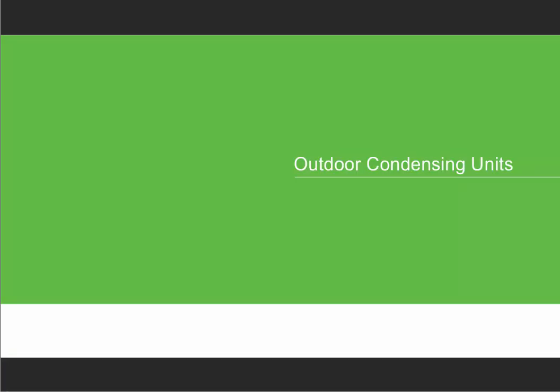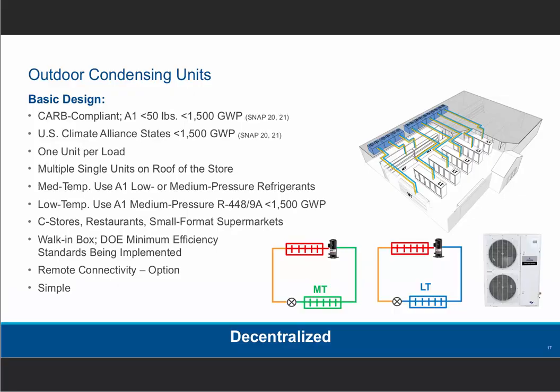But something that we've known for a long time, the beauty about your standard outdoor condensing unit is that they're well known. They're easy to work on. They're available from all the refrigeration wholesalers that you deal with. And parts are always available for these things. So that's one advantage. When you look at smaller loads, individual outdoor condensing units make a whole lot of sense. And we also understand that there are still a lot of retailers out there today that use individual condensing units. There's a lot of them out there in stores. And as an option going forward, it can also be an option to meet some regulations in certain parts of the country.